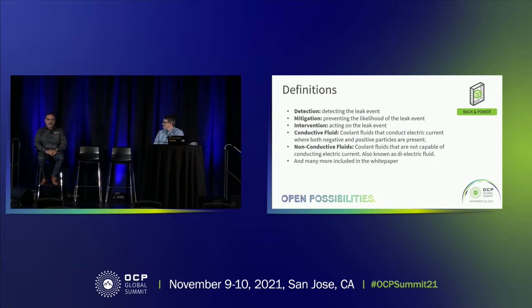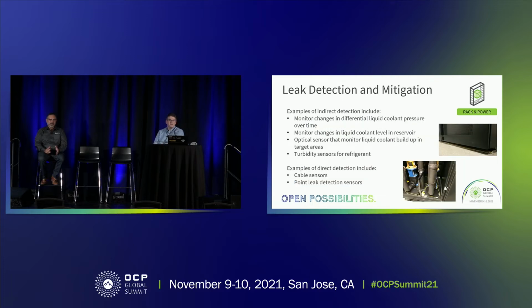On the refrigerant side of things, where I've seen some of the leaks in the systems is definitely at the couplings. Interestingly, sometimes the leak comes as a question from the customer, saying it seems like my cooling capacity has gone down. We'll go in, and usually it's more of an indirect method, but you can check the sight glasses on the inside of the CDUs and see where that fluid sits.